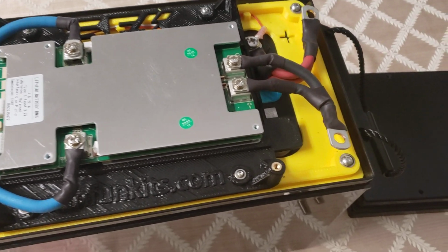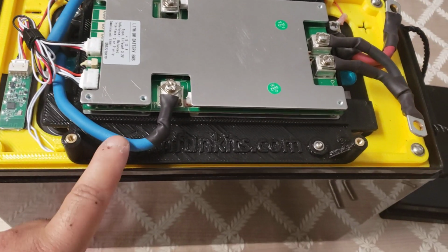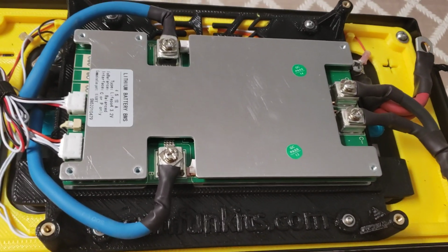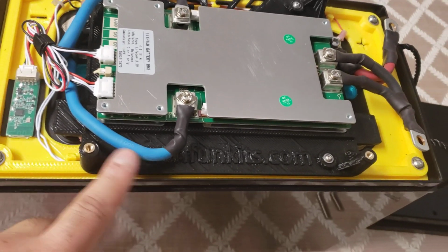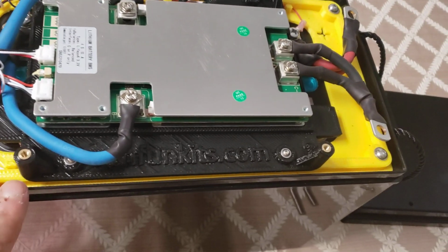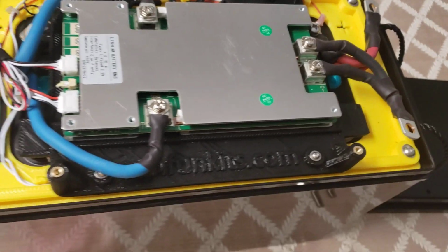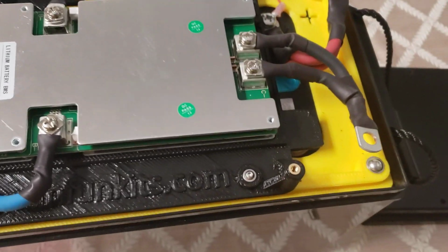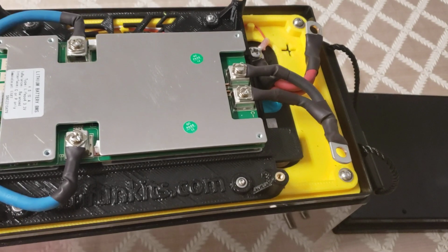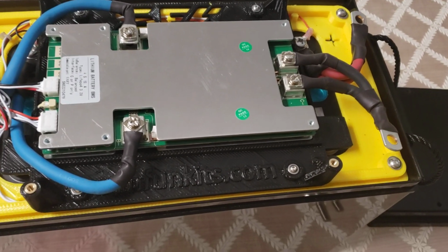The entire system uses 6 gauge American welding and battery cables. Each wire is rated for 75 amp continuous and is pure copper. The lugs are also pure copper tinned. So it is capable of providing up to 150 amps continuous.